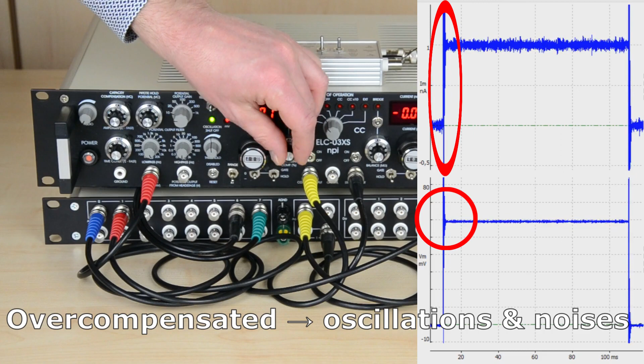To compensate this, switch on series resistance compensation and turn up the potentiometer. The theoretical optimum is at about 82% compensation. Overcompensation will increase noise and lead to oscillations.